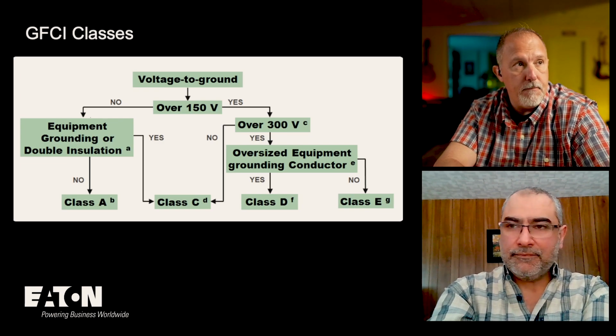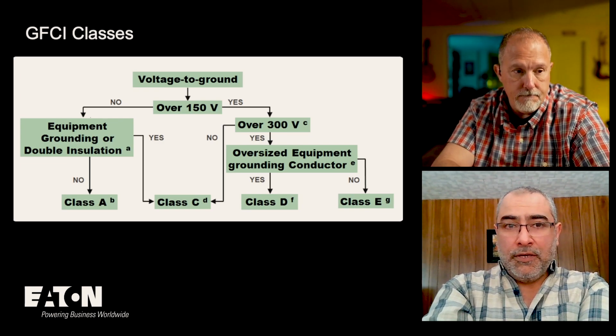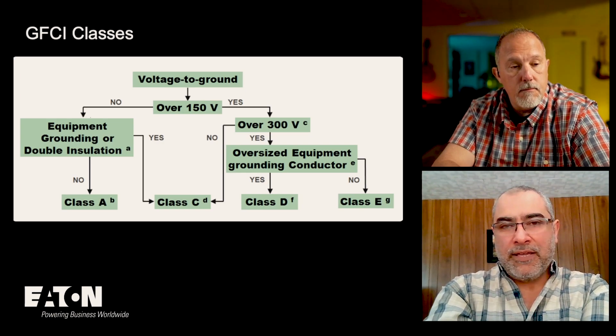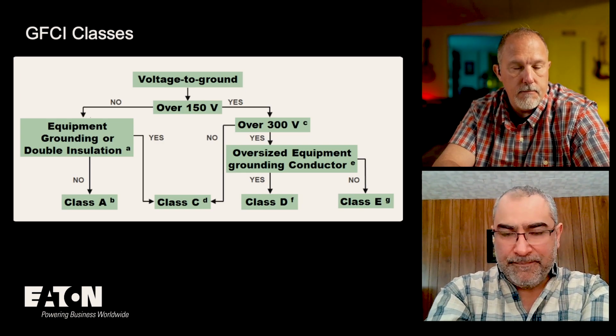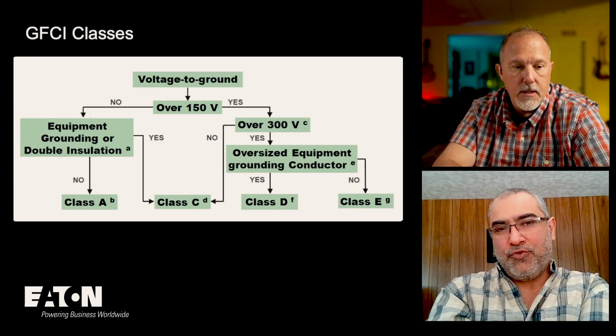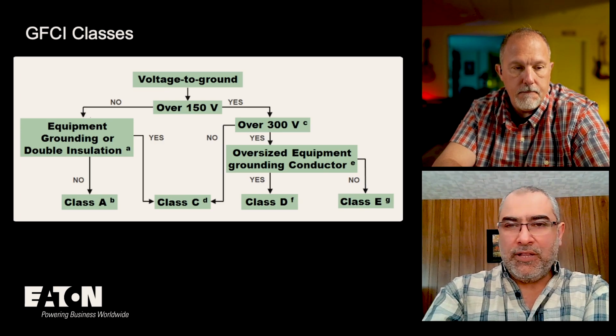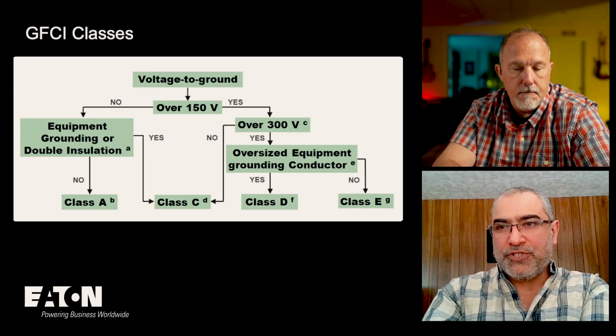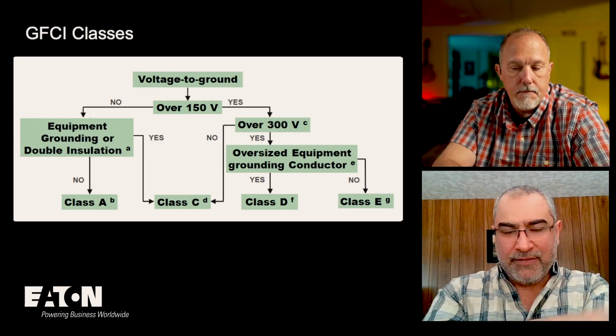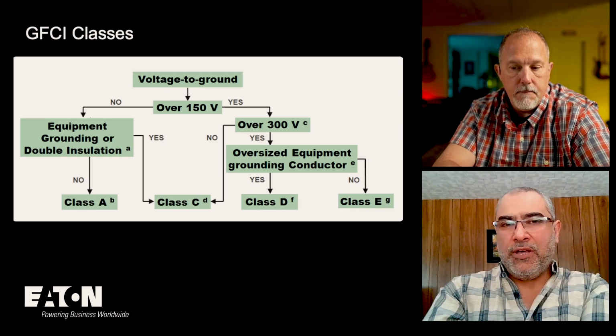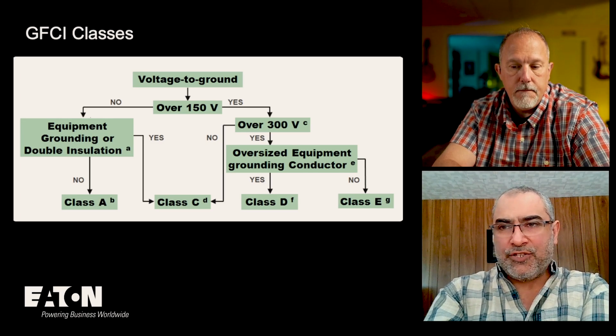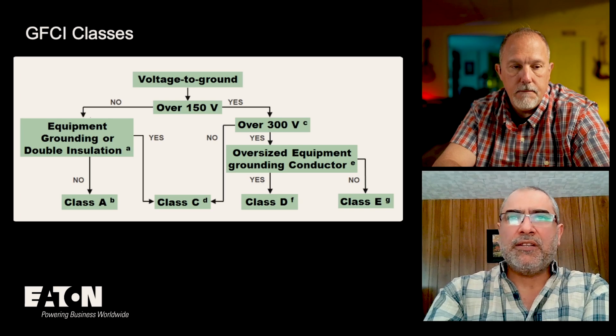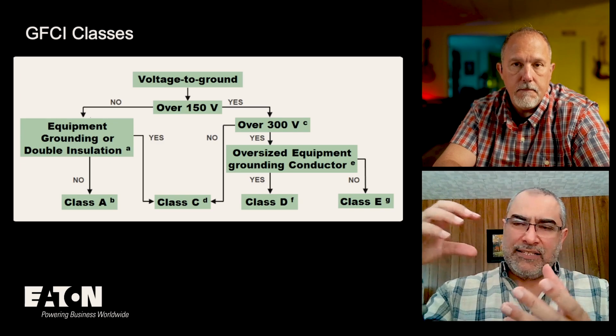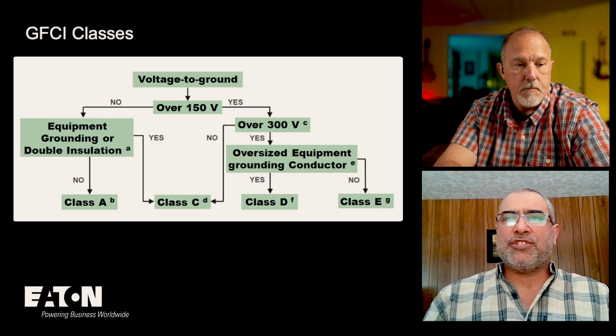Right. Yep. So do you want to explain this slide? Sure. So again, this came out of the UL 943C, and the C has nothing to do with the classes. UL has 943A, which is the Class A GFCI. So they dropped the A, and UL 943 is very popular. And then UL 943B is the standard for what they call the appliance leakage current interrupter, so devices used in, like, your hair dryers.